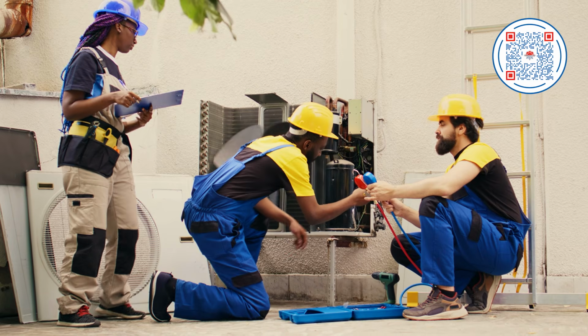Secondly, whenever we're talking about the equipment, another big thing we see a lot is refrigerant lines. These guys coming in on these $7,000 installs aren't pressure testing the line. When an install is done correctly, the pressure test ensures there are no leaks in that refrigerant line, so you're not just leaking refrigerant.